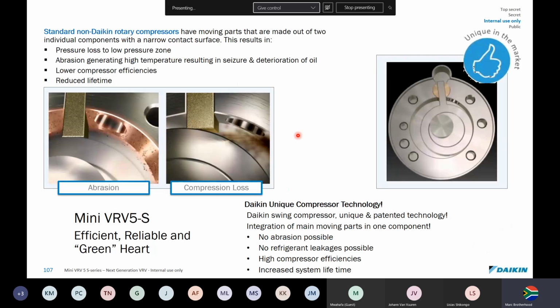Further technology that we use is, so the normal units use standard rotary compressors, or opposition who use non-Daikin rotary compressors, have moving parts that are made of 2 individual components. So this slide is going to slide up and down, and it's going to make a contact surface with this rotating, it's not a scroll, it's a rotary. So the problem is you're going to get pressure loss in a low pressure zone. As these geometries change, you're going to have different low pressures where you're going to get a pressure loss. You're going to have high abrasion, which generates high temperatures, ultimately leading to seizure of the compressor because the oil gets so hot and the oil also deteriorates.